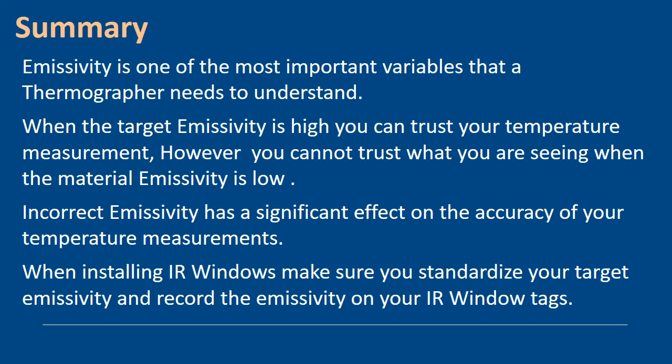When installing infrared windows, we teach that you should basically standardize your target emissivities and record those emissivities on your infrared window tags. So then you'll know your targets that are behind there, you've identified them, you've standardized your emissivity, you know the transmission rate of the window, so you're going to get good readings.